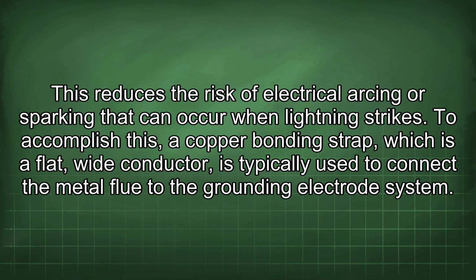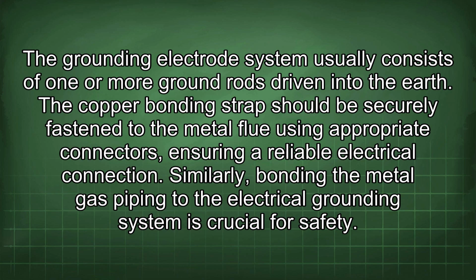To accomplish this, a copper bonding strap, which is a flat, wide conductor, is typically used to connect the metal flue to the grounding electrode system. The grounding electrode system usually consists of one or more ground rods driven into the earth. The copper bonding strap should be securely fastened to the metal flue using appropriate connectors, ensuring a reliable electrical connection.